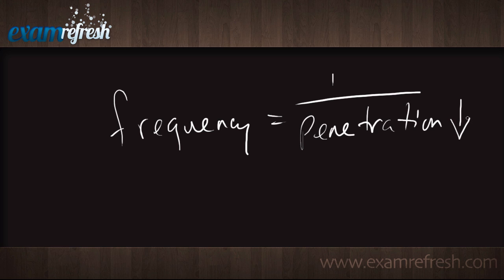Technically, our penetration is going to be down, because we only need to go a couple centimeters underneath the skin. What's going to happen to our frequency to be able to image well with a low penetration? Well, our frequency is going to go up. We're going to go from, let's say, 3.5. We're not going to use that to image a thyroid gland. We'll probably actually increase the frequency and go up to maybe a 10 MHz transducer or even a 12. So if the frequency goes up, that's going to cause our penetration to go down. But the whole reason you do that is because our resolution will increase, which is what we want.